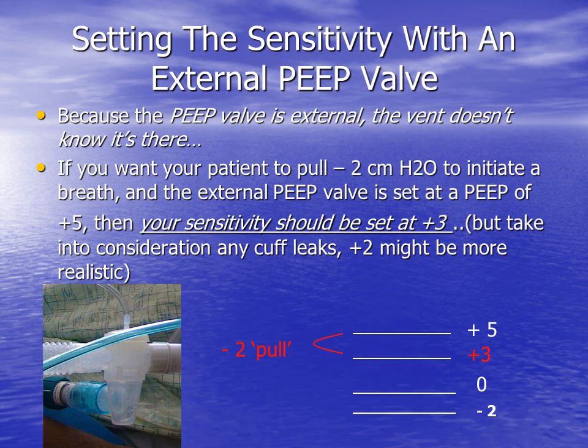Setting the sensitivity on any vent circuit that utilizes an external PEEP knob can be tricky. Again, the knob is external and the vent doesn't know the pressure is there. It's adding extra pressure in the circuit that will trick the ventilator. So in this example, you want your patient to receive a breath after a -2 centimeters of water pressure pull. So you set the sensitivity at -2. The vent will monitor pressures in the circuit, and when it sees -2, it will deliver a breath.